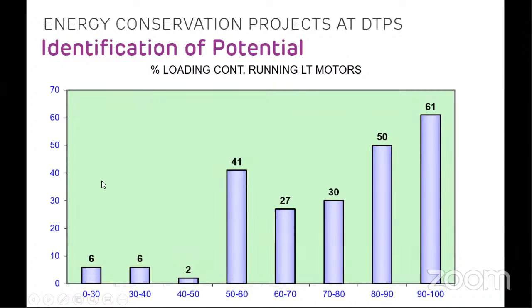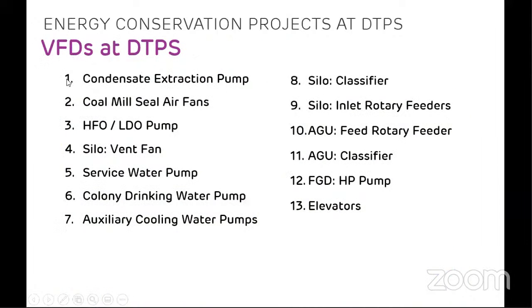Similarly, we carried out the survey for LT motors. Here you can see a good 61 motors were properly designed and running at full load. The rest of these motors were running at lower than their rated capacity. So they have a very good scope for VFD application. Finally, we found that these 13 motors are very suitable for variable frequency drive applications, which included condensate extraction pump, coal mill seal air fans, and so on until elevators.